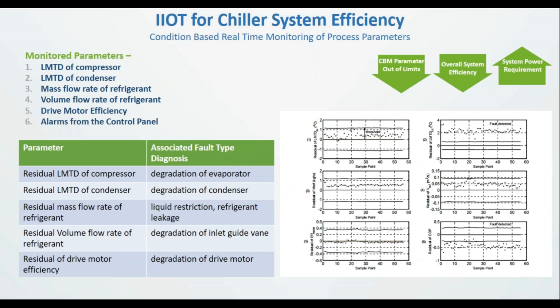If you see on this slide, we've mentioned certain critical parameters like LMTD of compressor, condenser, mass flow rate of refrigerants, volume flow rate. We can have individual sensors for each of these critical parameters, and they'll be monitored real time. The idea being that if a particular flow rate is critical for the performance of the equipment over time, we're able to define upper and lower control limits for that parameter and a target value, and monitor the actual value of the equipment versus those set limits.